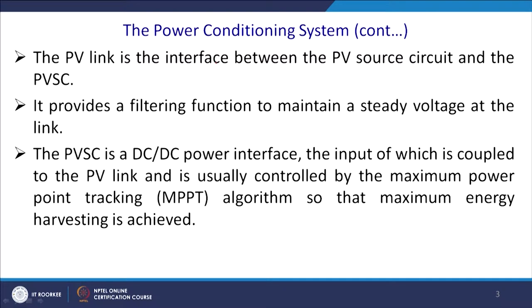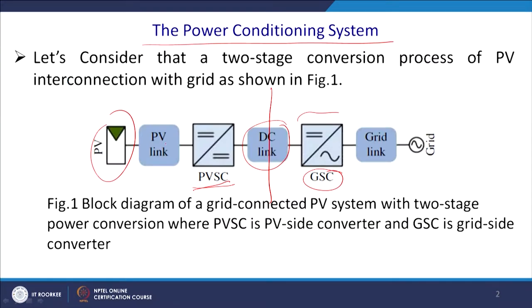The PV link is interfaced between the PV source circuit and the PV side converter (PVSC). Since the converter involves switching, we require filtering. In a buck converter, for the interval when the switch is off, you are stopping the current, which can shift the MPPT point. Thus you require to sink some amount of current in a capacitor, resulting in a ripple. The PV link — a combination of capacitor and inductor — gives a ripple-filtered voltage at the input to the PVSC.